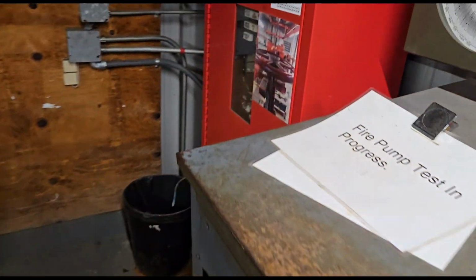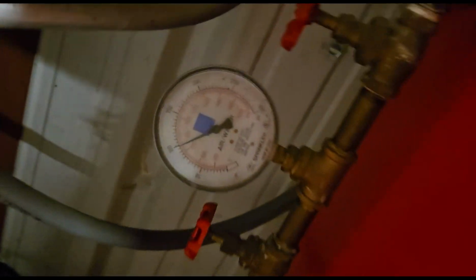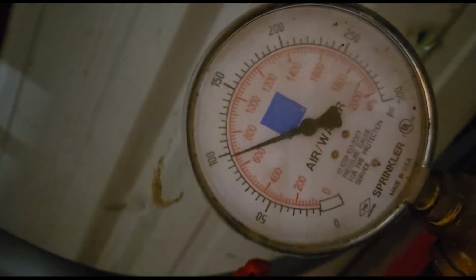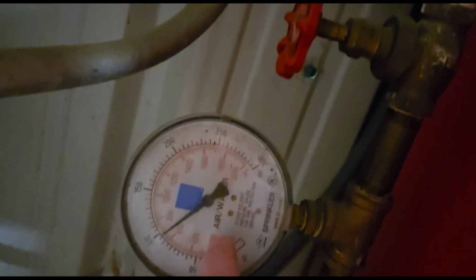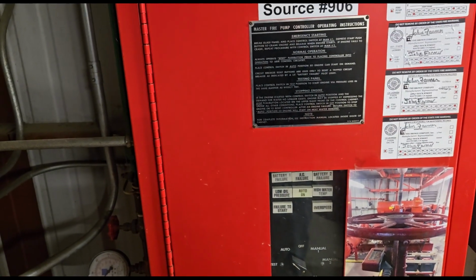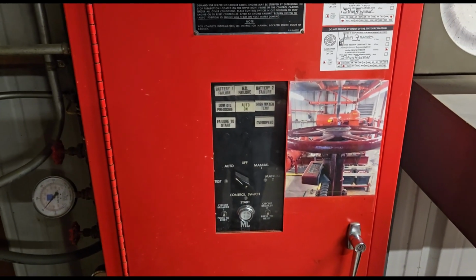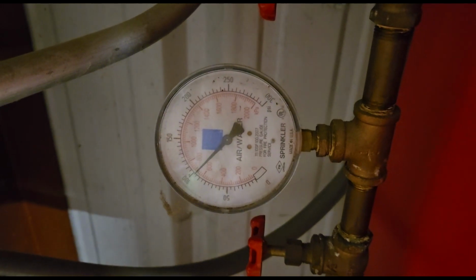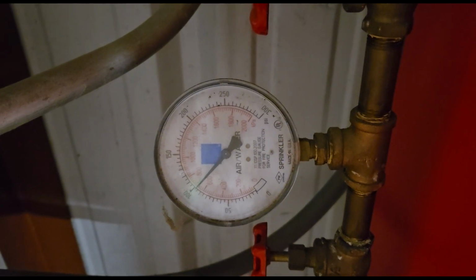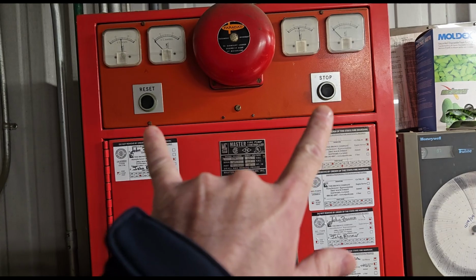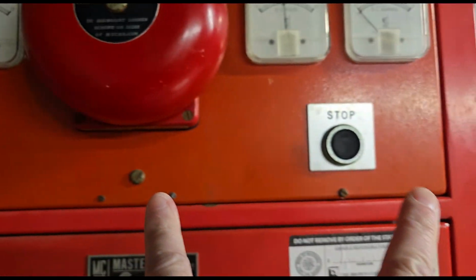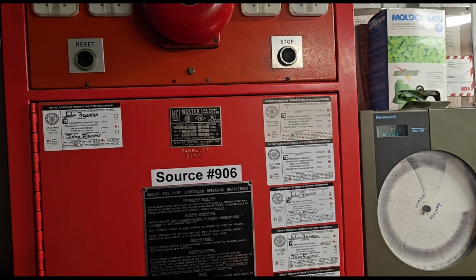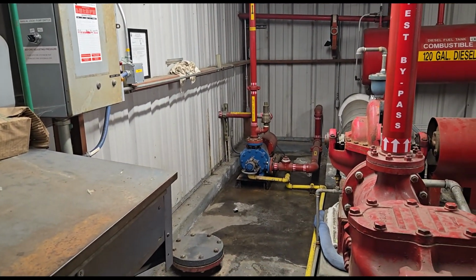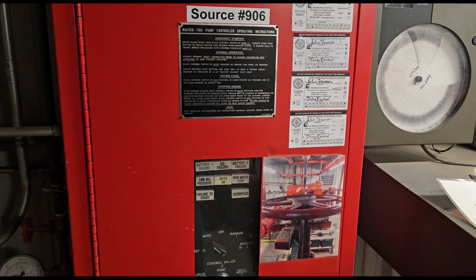So we're going to take note of our PSI. Looks like we're at 100 PSI. All right. So when we come back to turn it on, we want our PSI to be back up to its original state. Otherwise, if we try to turn the pump on with the PSI low, the fire pump will turn on. So we'll have to turn it off. In which case we have a reset and stop switch up here. So your reset and your stop. We'll just have to basically stop the pump, let the jockey pump continue to fill up the pressure before we turn this pump back on.